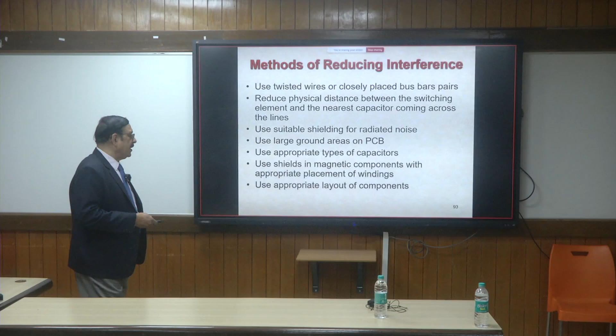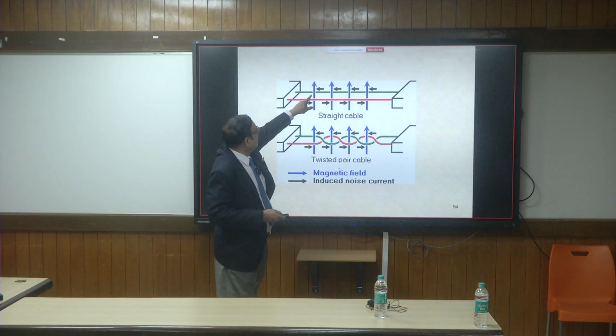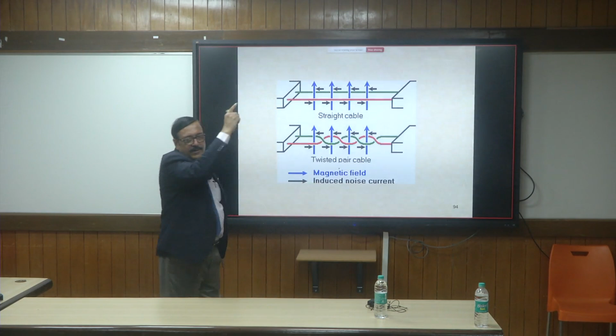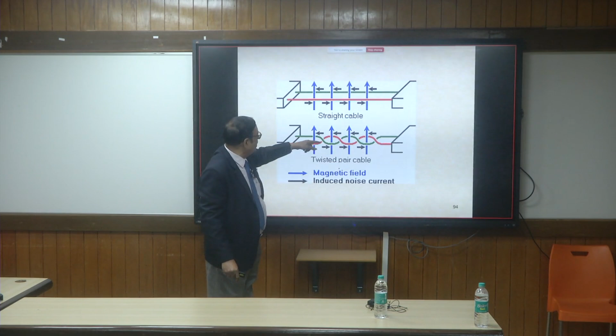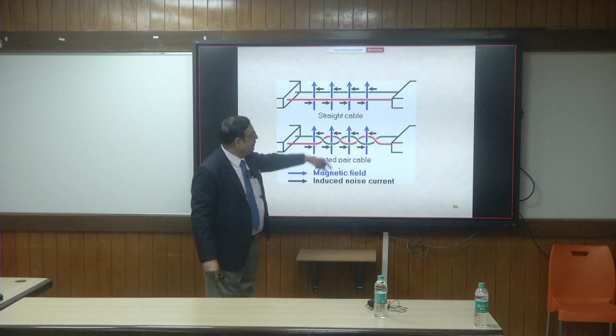This is an example from published data showing how twisting helps. You have a straight pair of conductors between two elements, with a stray field shown by the blue lines coming in. Here it's totally coupled, as if this is a loop with flux going right through. If you twist the conductors, the couplings break up and the end result becomes zero—for the green conductor, it's coupled on one side and in the other direction on the other, so the effect cancels out.